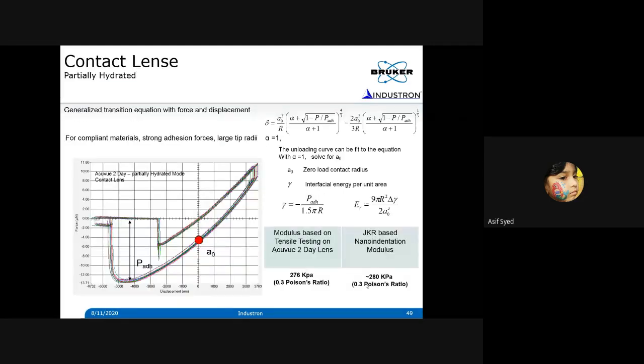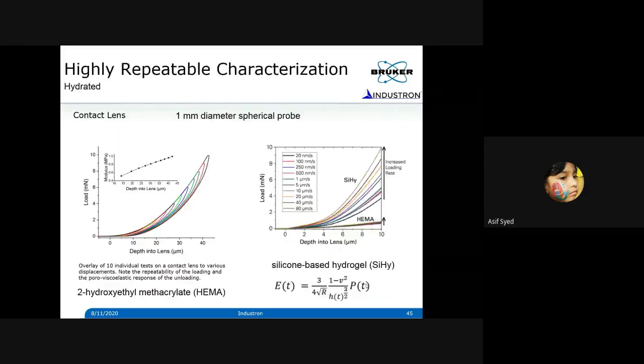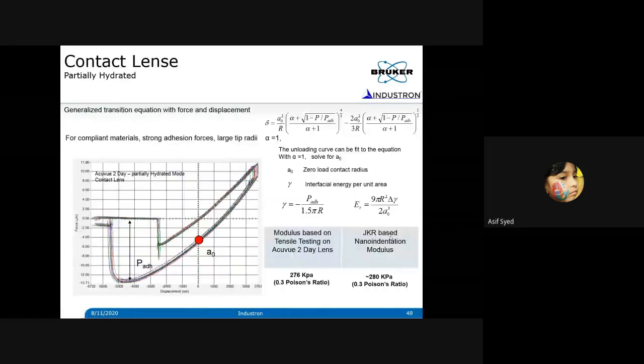Now, when you do it in a partially hydrated state, like I mentioned, you don't get this nice load displacement curve the way that you wanted to get, right? When you do a partially hydrated or a dry condition, you will see this kind of load displacement curve. This is the curve that I started with in the beginning. When you have soft materials, and you have this kind of curve where the tip jumps into contact and then loads and unloads, you cannot use those adhesion contact mechanics anymore. You need to have this modified JKR method that I mentioned, and you can fit the unloading curve and extract the modulus of the material as well as the surface energy of the sample. You can do both of that.